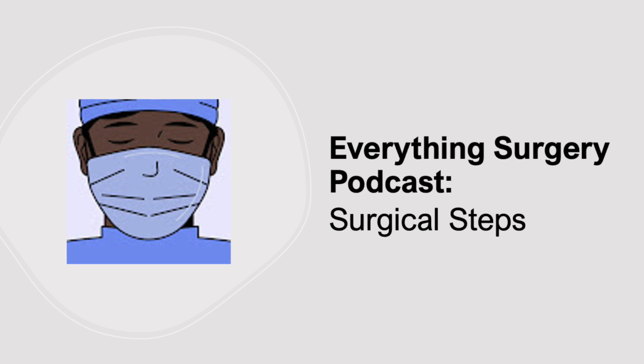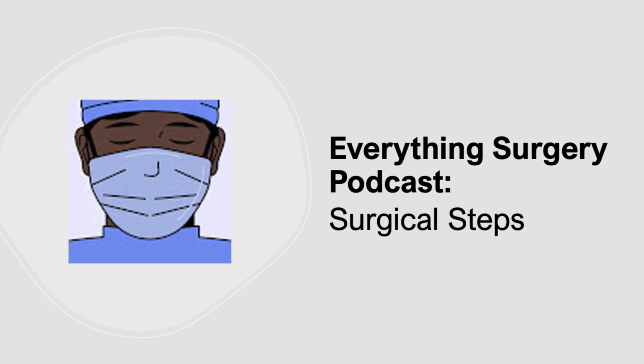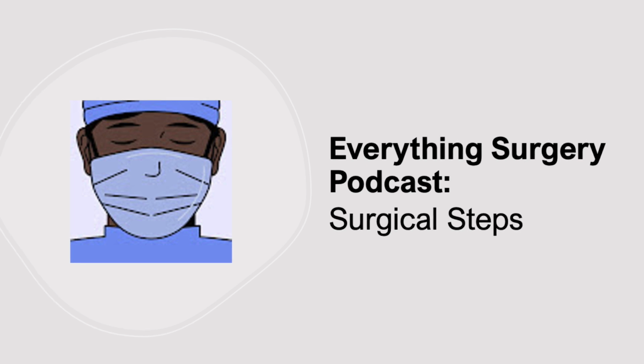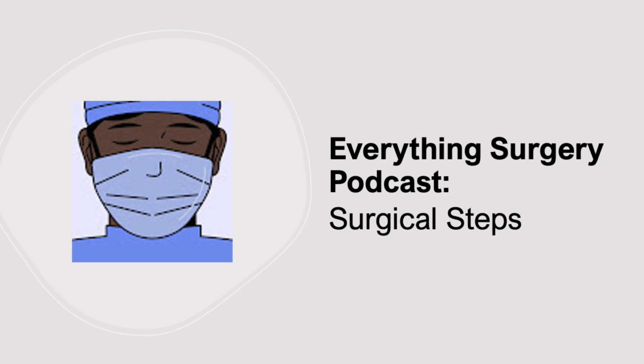Imaging system setup. Alright, moving on to the imaging system. First, attach the laparoscope to the camera head. Super straightforward. Then connect the camera control unit, CCU, to the monitor. Here's the kicker: adjust your image settings. You'll need to perform a white balance. Just point the scope at a white gauze and hit that balance button. Nail the focus, and make sure your HDMI or SDI cables are playing nice if you are recording digitally. Boom, your visuals are ready.